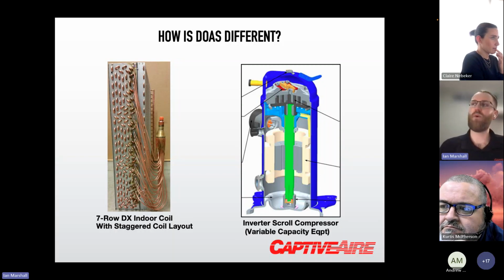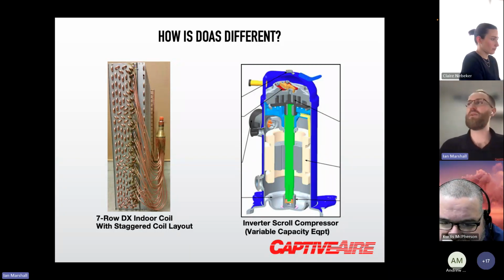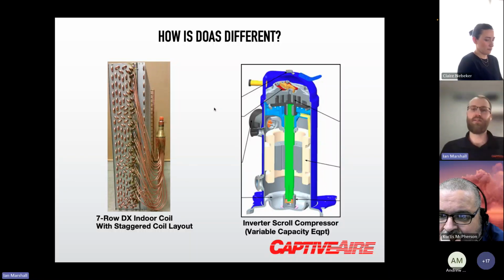So we use this staggered coil design to essentially pull out moisture, and there's no straight pass through for the coil. So that air is kind of forced to be turbulent and touch as much surface area of the coil as possible. And then we utilize the hot gas reheat coil in many cases to reheat that air back up. So that's the first component. The second component would be the compressor.